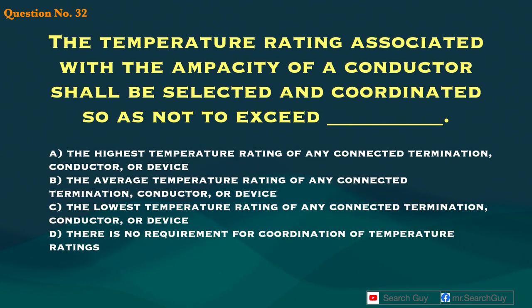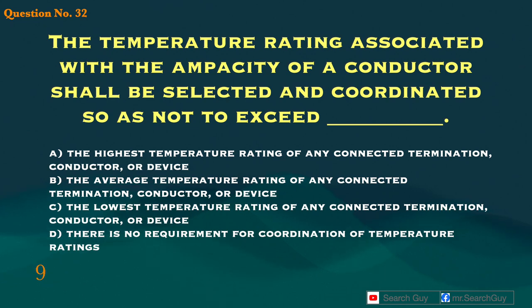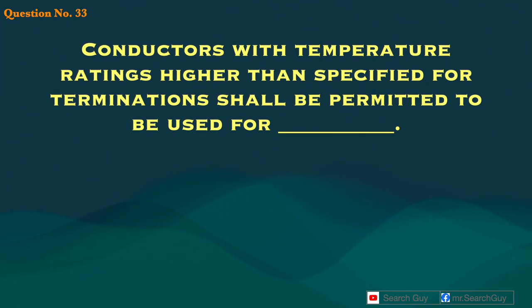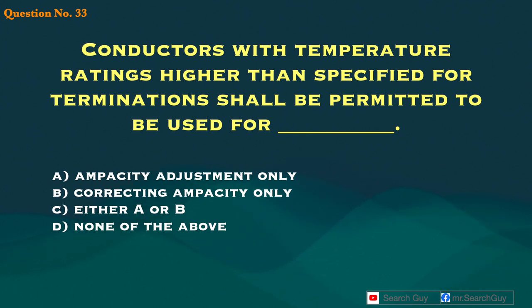Question 32. The temperature rating associated with the ampacity of a conductor shall be selected and coordinated so as not to exceed blank. A. The highest temperature rating of any connected termination, conductor, or device. B. The average temperature rating of any connected termination, conductor, or device. C. The lowest temperature rating of any connected termination, conductor, or device. D. There is no requirement for coordination of temperature ratings. Answer: C. The lowest temperature rating of any connected termination, conductor, or device.